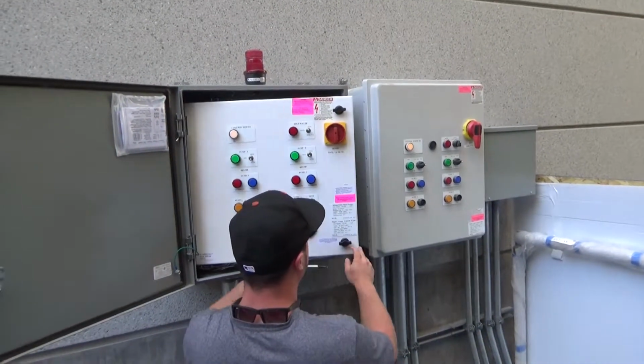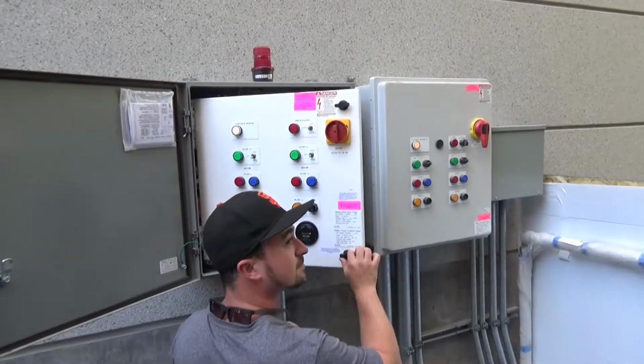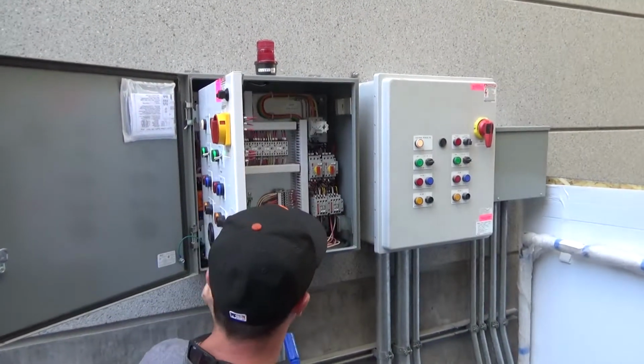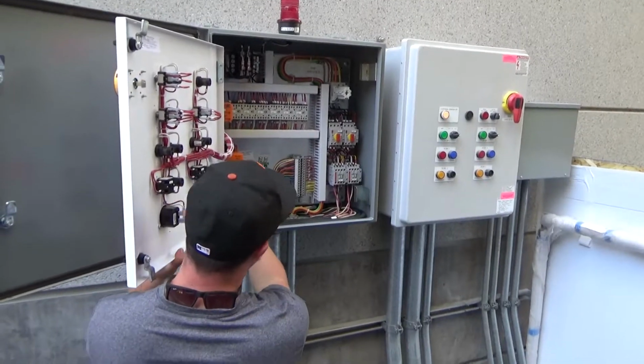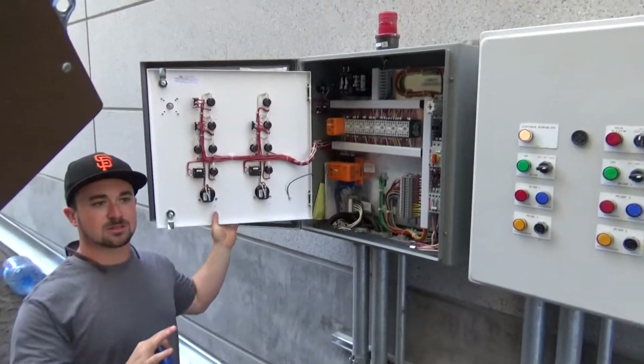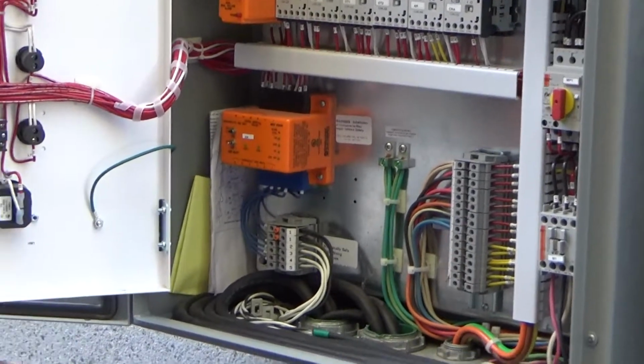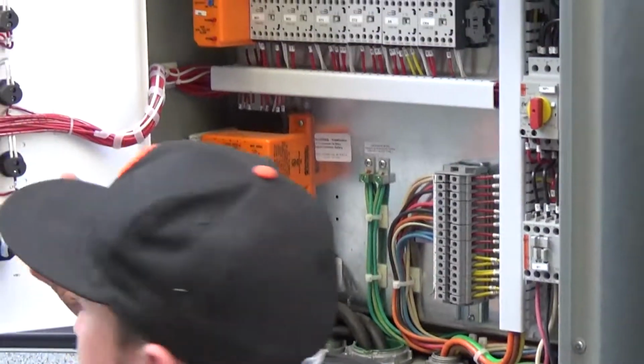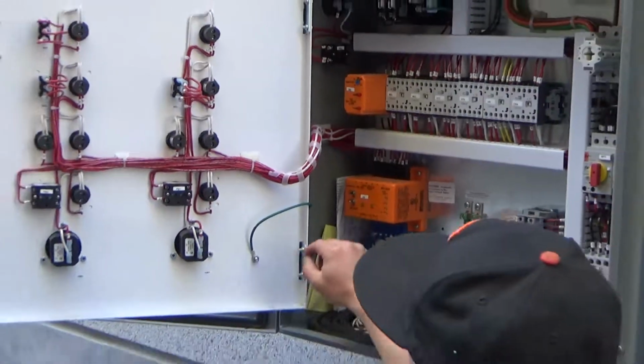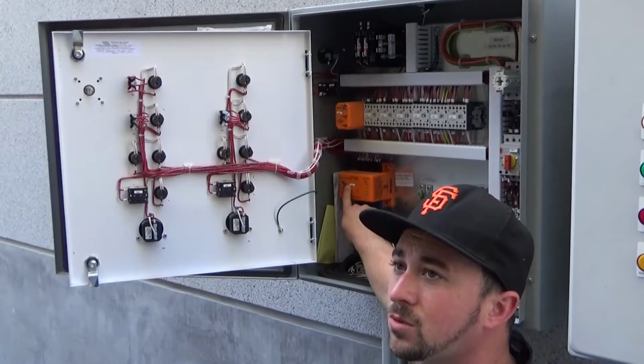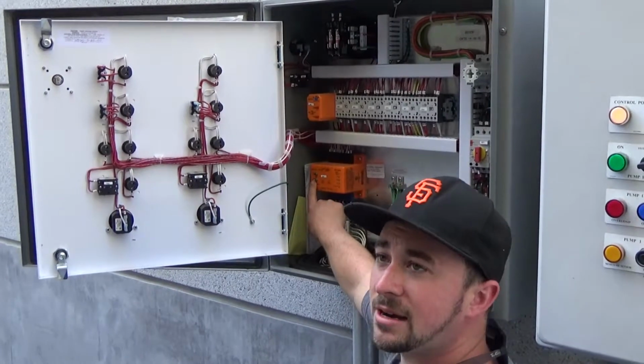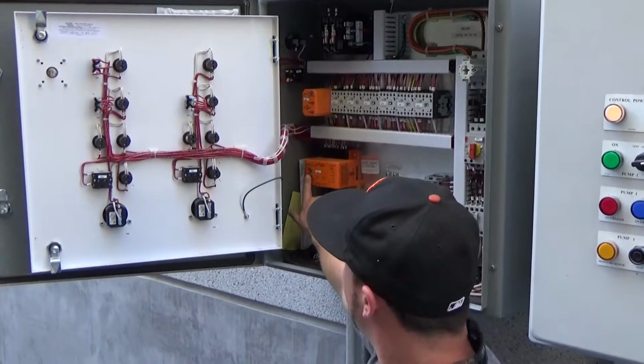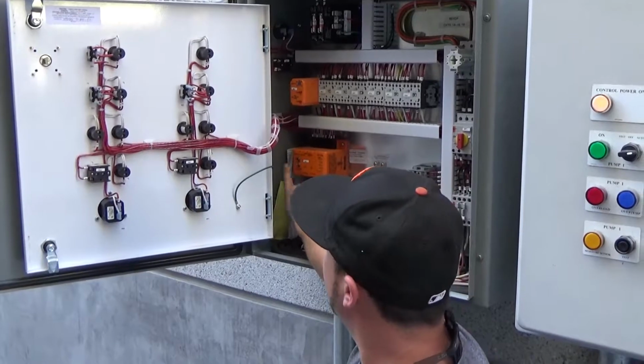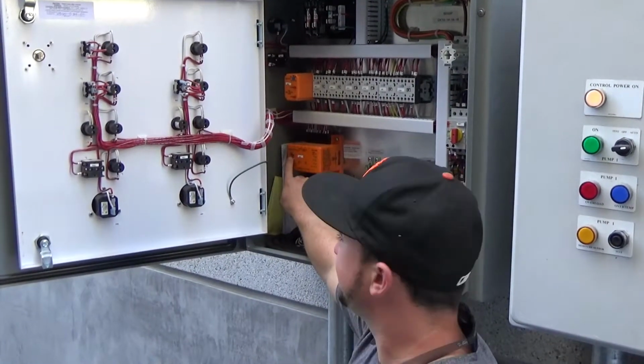What about, leave that open, the indicators for the pump running, I see there's a test button on the left there. Yes, sir. What are those all about? So, say pump 2 is, you guys have to send that back somewhere. You're getting it worked on or something like that. And you don't want to do the lead lag function because you only have one pump in the sequence. Okay. So load 2 would be pump 2, load 1 would be pump 1. And the center would be auto. Right now it's auto because it's jumping around between both. But I only have pump 1 now because pump 2's gone. Put it in load 1, pump 1.